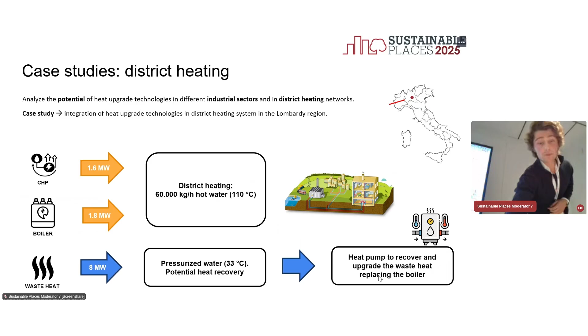The heat pump, since there's a very high lift from 30 degrees to more than 100, was modeled in EES, a similar software, as a double stage compression heat pump plus vapor compressor for the high lift. The results show that depending on the availability of waste heat — in the normal scenario, availability is just 7,000 hours per year — the heat pump would provide savings of around 300,000 euros per year.